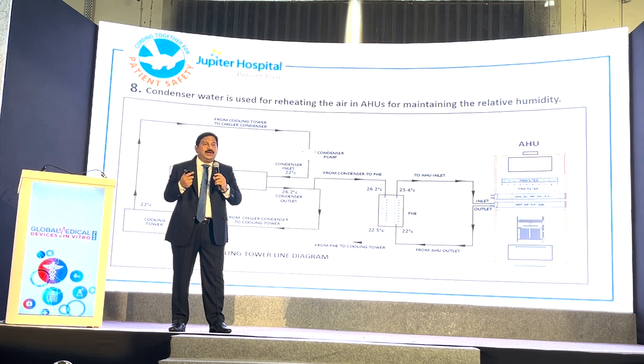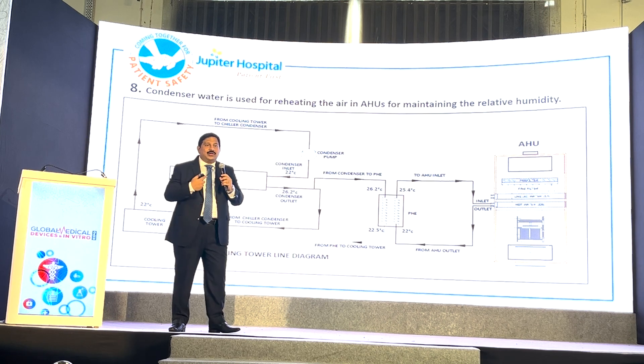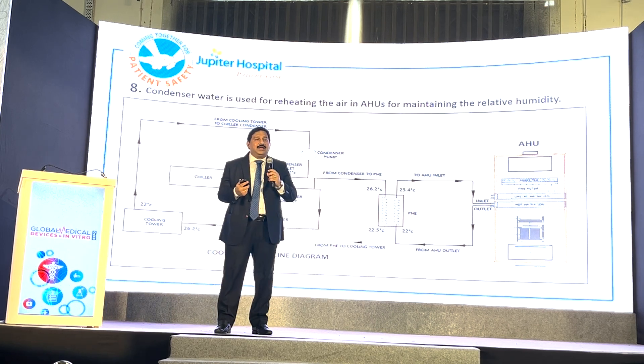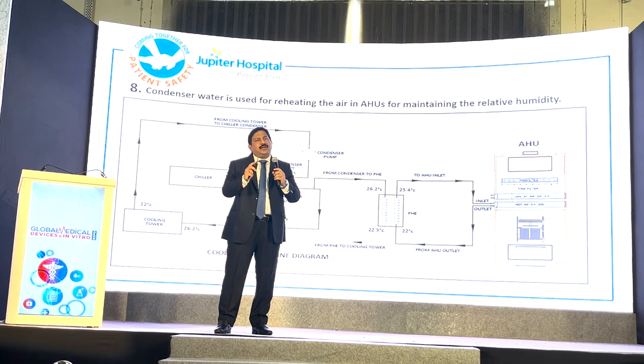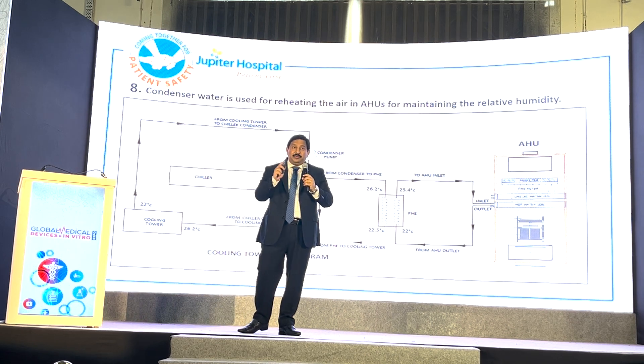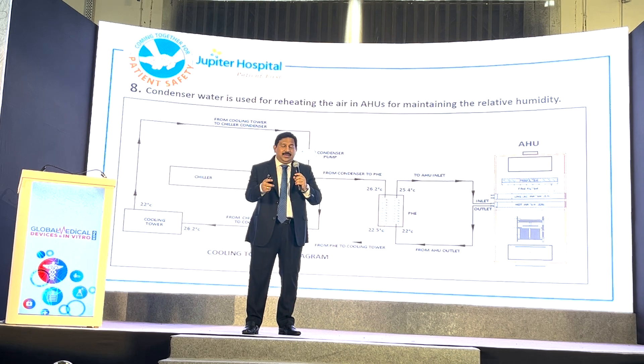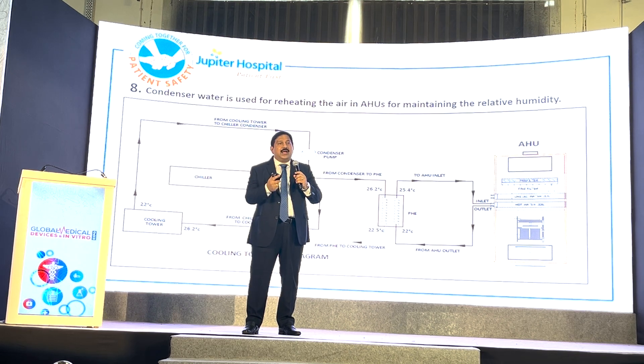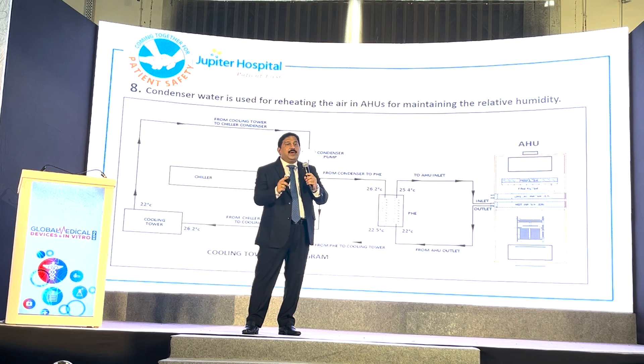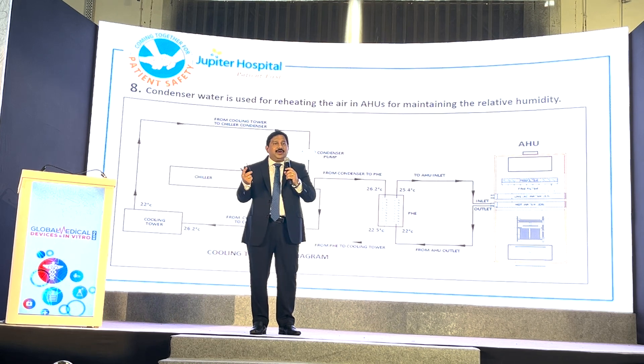But where has 22 degrees come from? Because I have worked in the US for that as well, and I have seen that their original data sheet will say the temperature requirement is 26 degrees. Just see that. Now if you are maintaining at 22, and last week I was in Delhi talking about energy-efficient medical equipment — CT, MRI, cath lab — everyone is saying there is a fixed 22 degrees, so what to do?